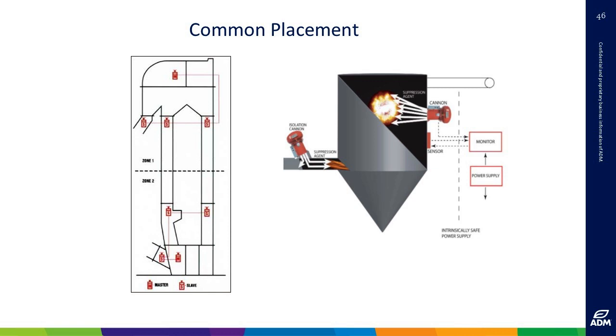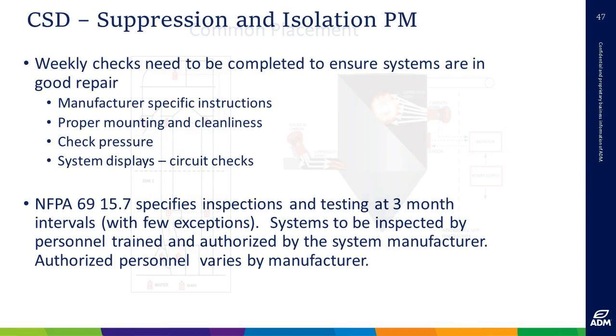For suppression, what we do is weekly checks. But I did want to call out that in NFPA 69, the suppression standard that NFPA 61 and 652 refer to, it specifies that inspections of suppression systems are done every three months. Most manufacturers, in fact I don't know of any, at a minimum require their folks to come in at least once a year, and OSHA will enforce that.